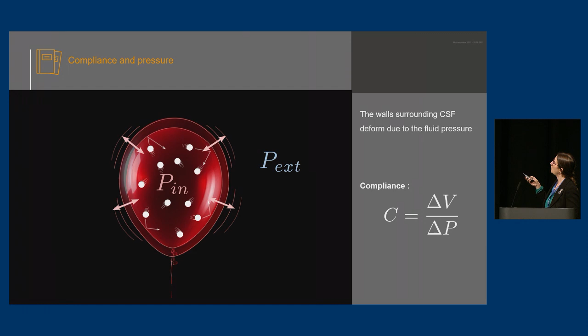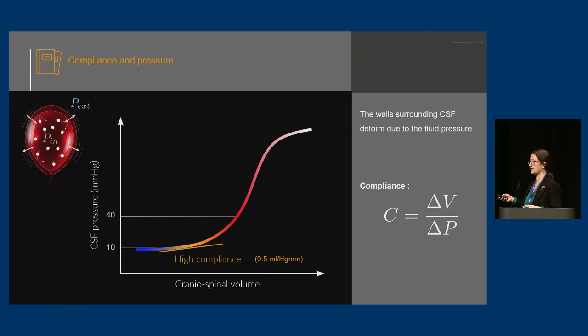What we see is that for small CSF pressure, we have high compliance, typically 0.5 milliliter per millimeter of mercury. But when you increase the CSF pressure, the compliance decreases. So we have a more stiff system, and the same change of volume will lead to a larger change of pressure. Usually we can explain this in a biological system because of the mechanical properties of the wall.